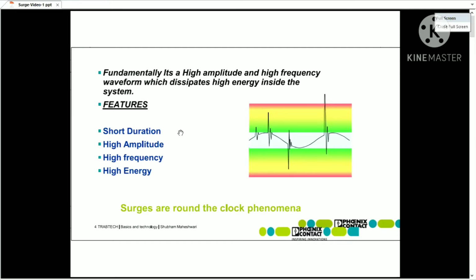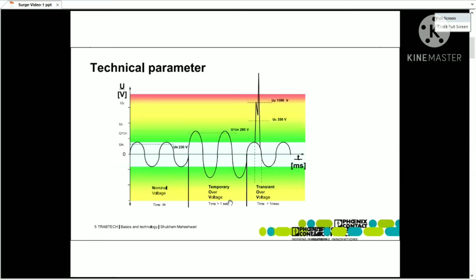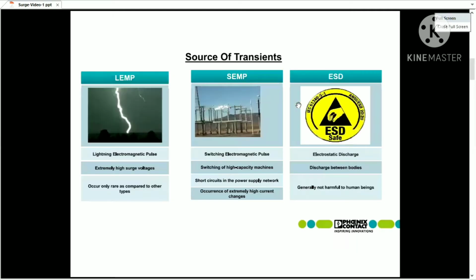Surges are transient or short duration, high amplitude, high frequency, high energy waveforms which can transfer this energy into an electrical system. These surges typically last between 20 to 350 microseconds and range in amplitude from 350 to 1500 volts. There are three sources of these transients: lightning, switching, and electrostatic discharge.